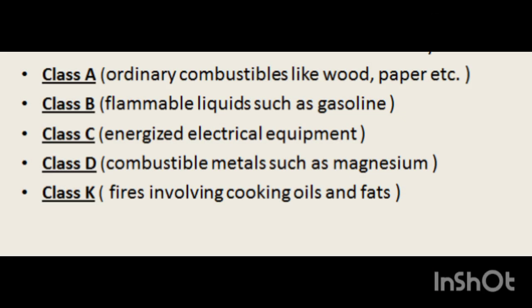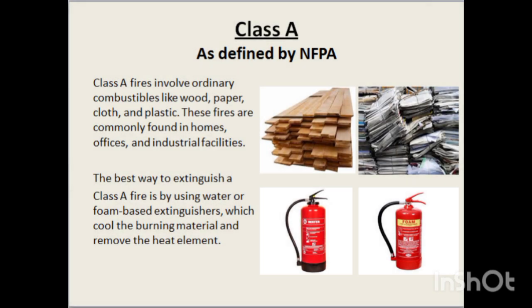Class A fires involve ordinary combustibles like wood, paper, cloth, and plastic. These fires are commonly found in homes, offices, and industrial facilities. The best way to extinguish a Class A fire is by using water or foam-based extinguishers, which cool the burning material and remove the heat element.